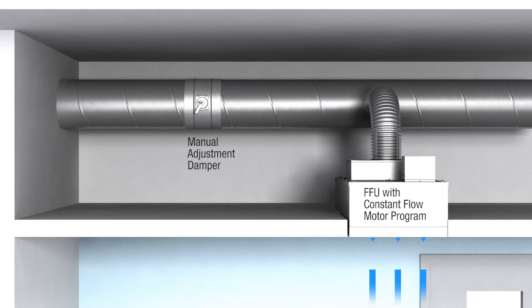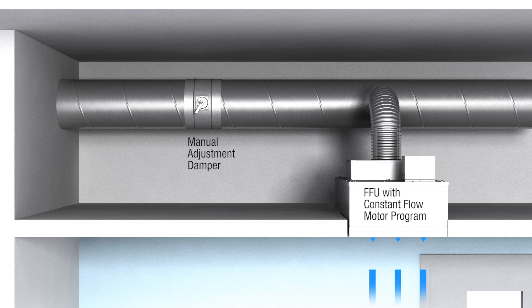An FFU with a constant flow program should not be directly ducted to an upstream pressure independent terminal device, as this causes both smart devices to fight for control and can lead to airflow oscillation and poor performance.